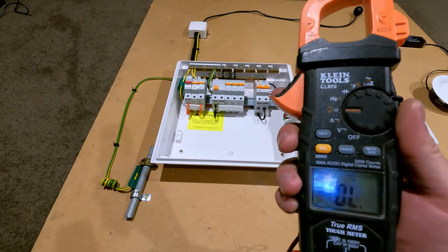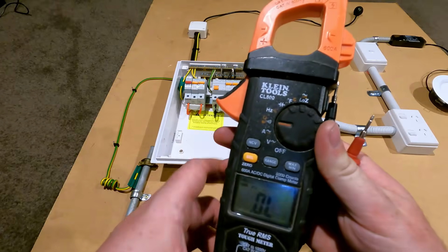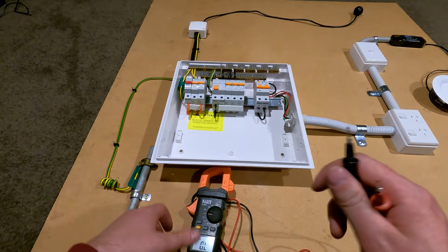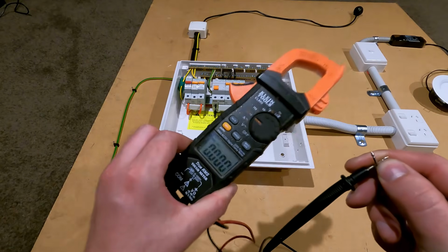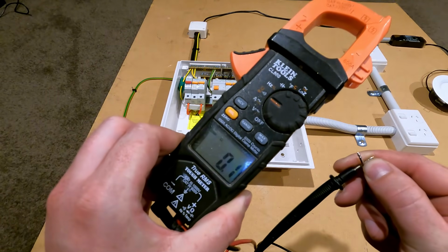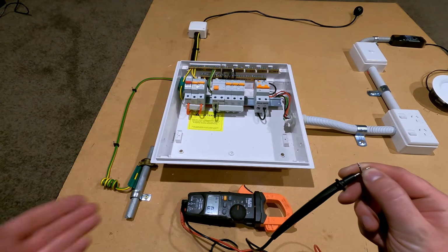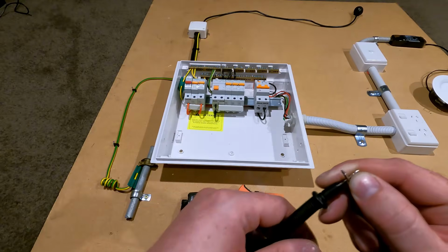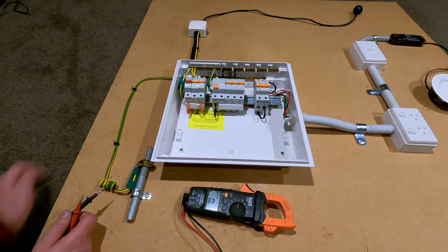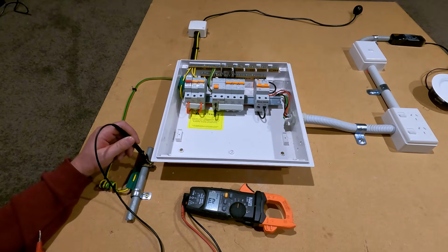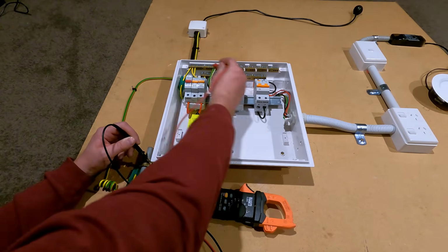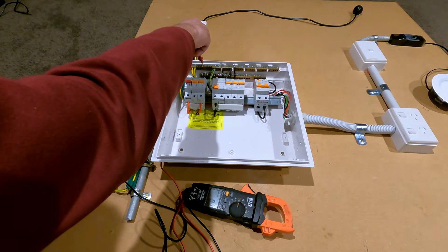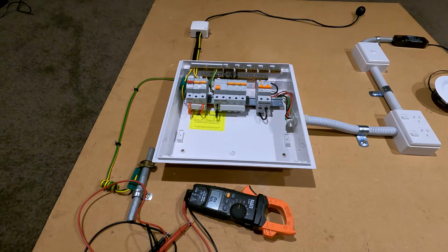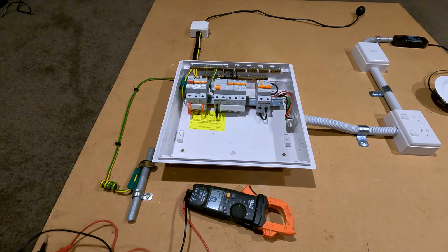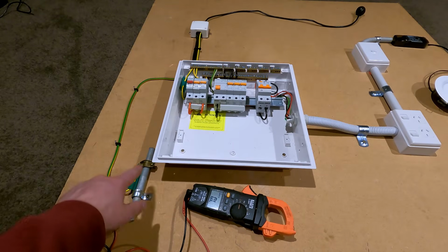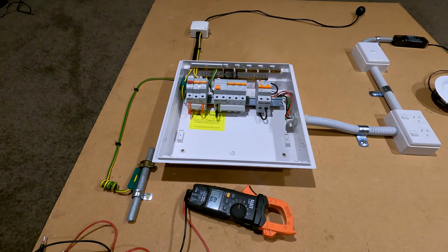Throw the meter onto ohms, take it off continuity, and put it on ohms measurement, and we're going to test, firstly, put the leads together and see what the resistance is. So we've got 0.1 ohm. We're going to subtract that from our measurement we take between the earth bar and the earth stake. So what we're going to do here is test from the earth clamp back to the main earth bar. So our result was 0.1 ohm, which was the same resistance in these leads. So it's negligible how much resistance is actually in this cable. Obviously less than 0.1 ohm, which is perfect.